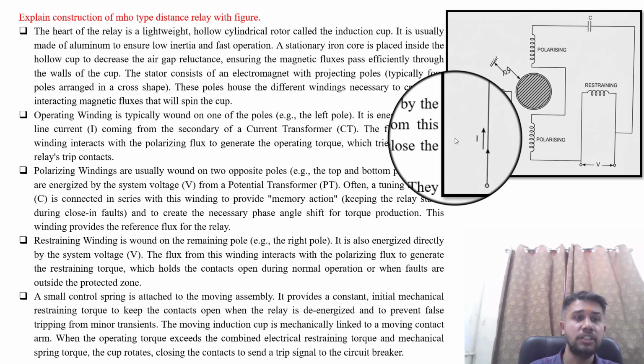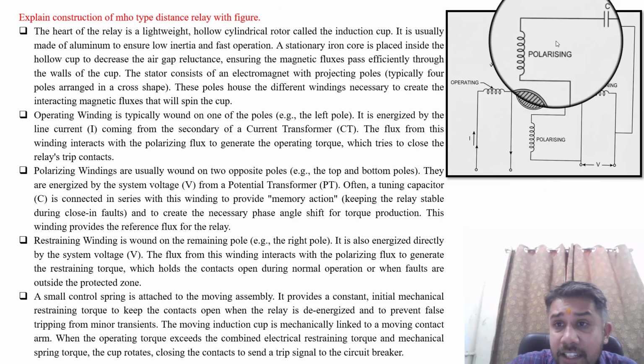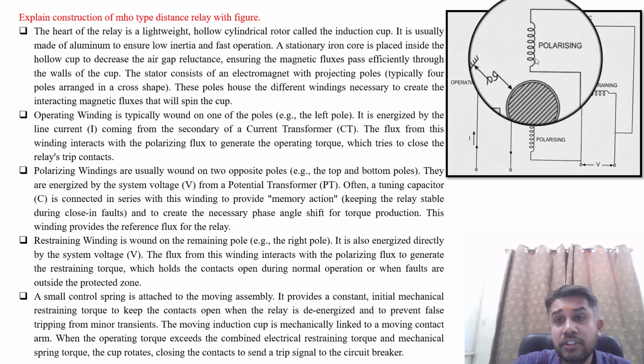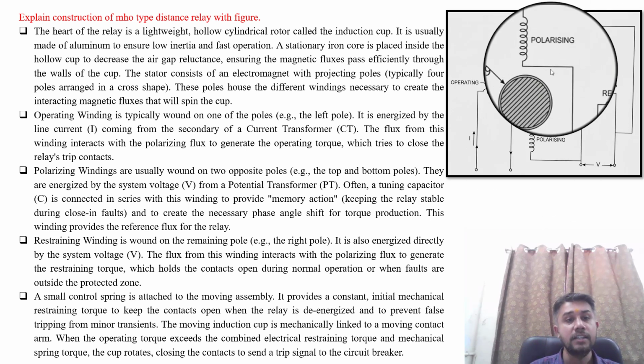The flux from this winding interacts with the polarizing flux to generate the operating torque, which tries to close the relay's trip contacts. Now the polarizing windings, here you can visualize these polarizing windings. These are usually wound on the 2 opposite poles, that is the top and the bottom poles here. They are energized by the system voltage from a potential transformer, PT.